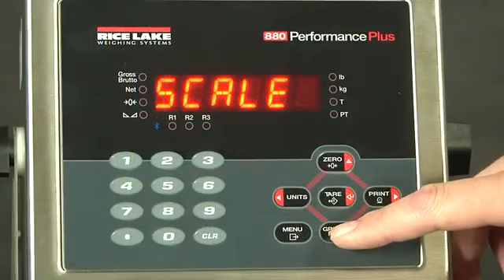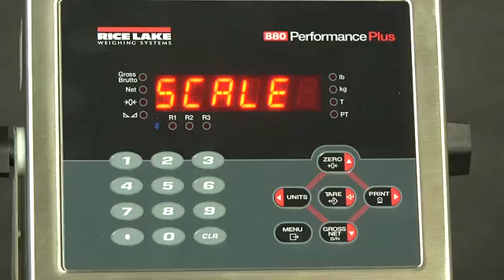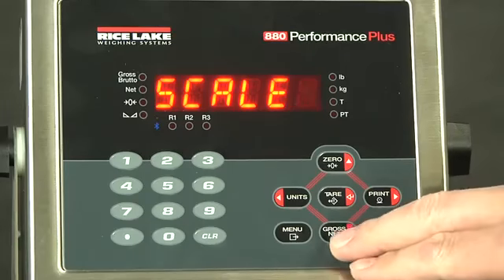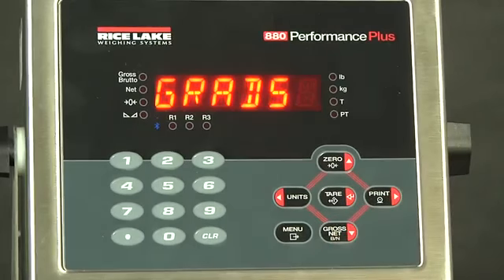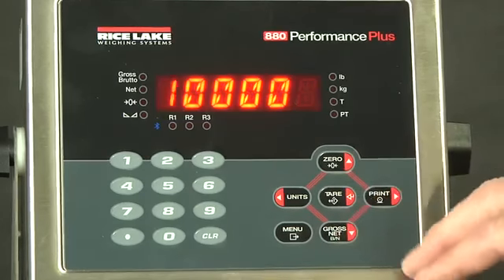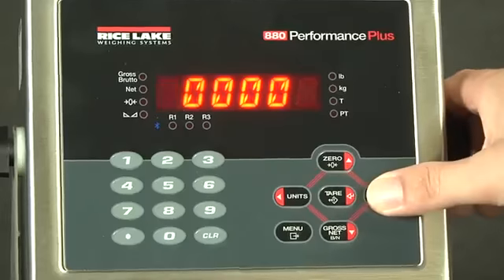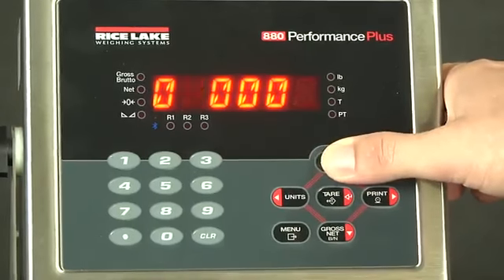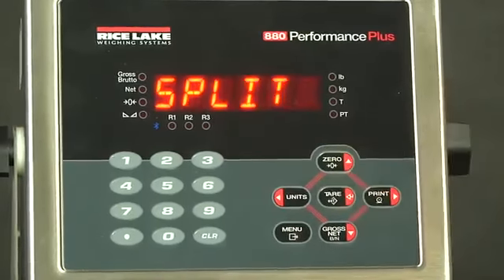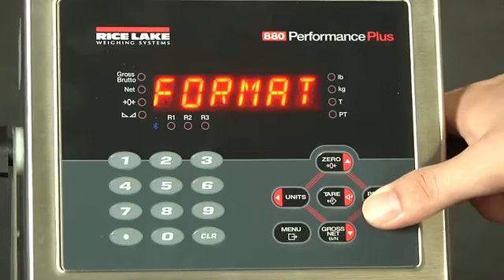From there you drop down, and here we have the scale's parameters. This is where we will configure anything that has to do with the scale. So as we drop down again, grads is our first available option. Since we are doing a 5,000 pound scale by 1 pound, our graduations will be turned down from 10,000 to 5,000. Now we come to the split parameter. That is unneeded. We will move on.